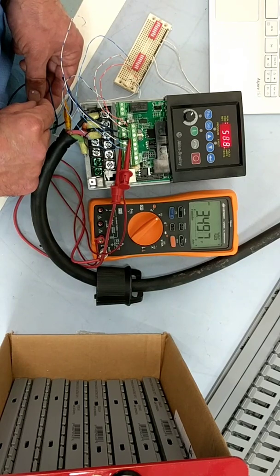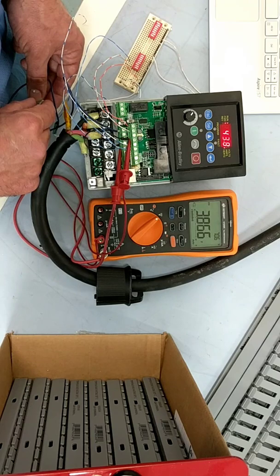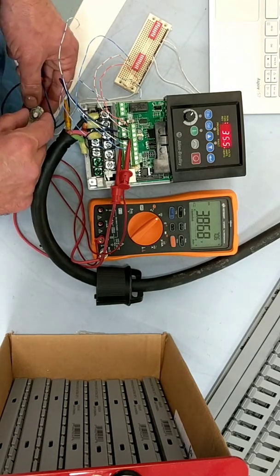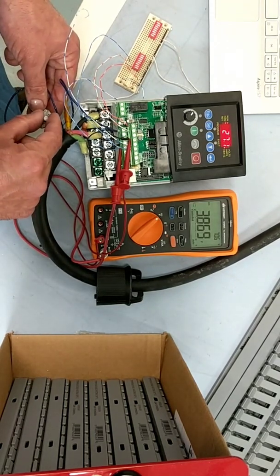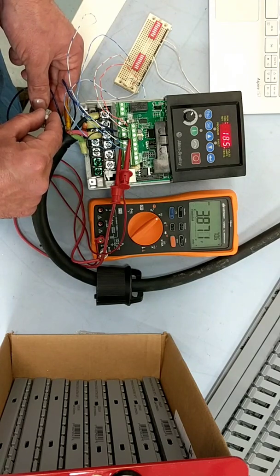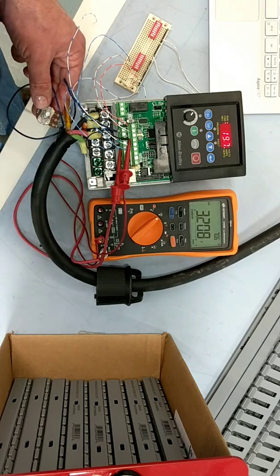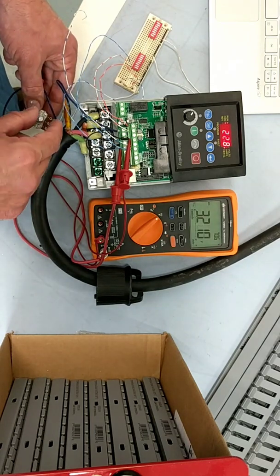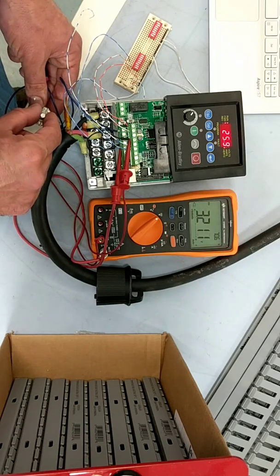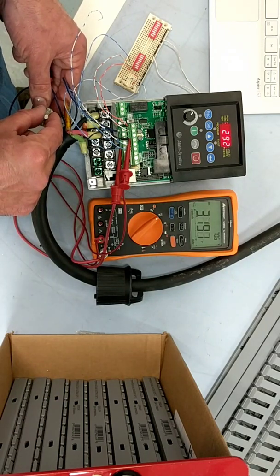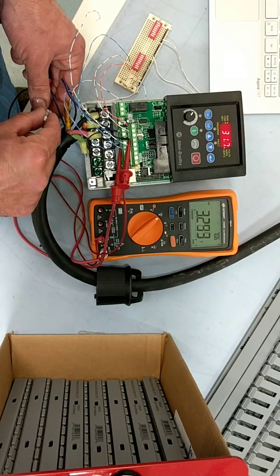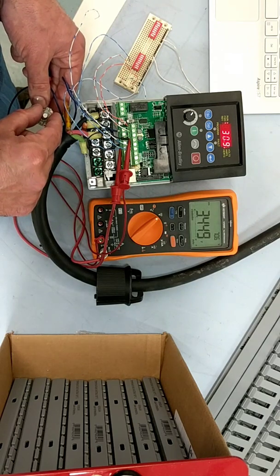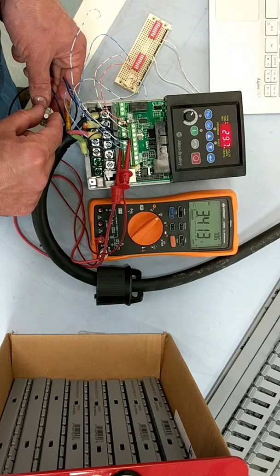And there we are, 3.8, and it's moving pretty quickly back down. And then I'm going to adjust the potentiometer to something lower than 3.4, and we'll see the drive increase in speed now. And there it's going back up. I'll try and stop it somewhere in the middle. Right at 3.4, there's going to be some dead zone where the drive doesn't change at all.